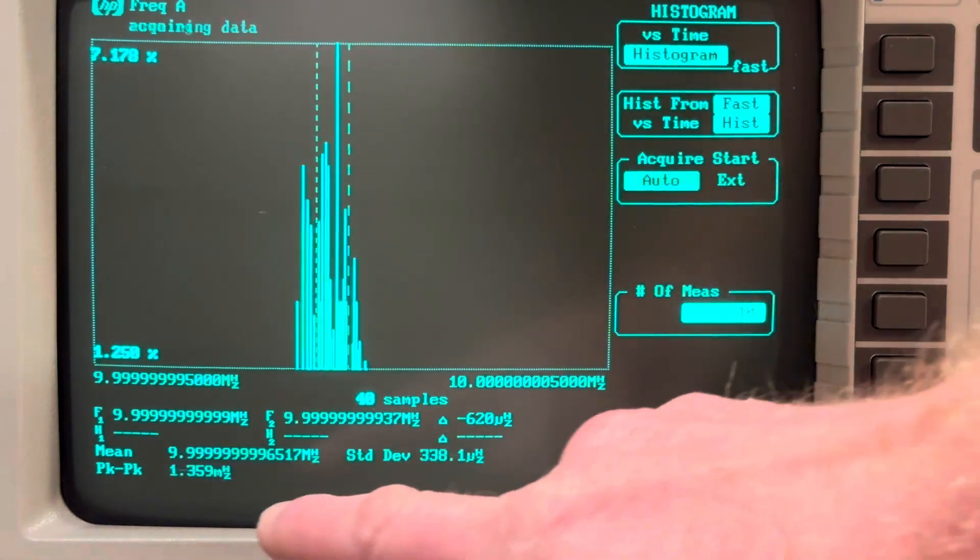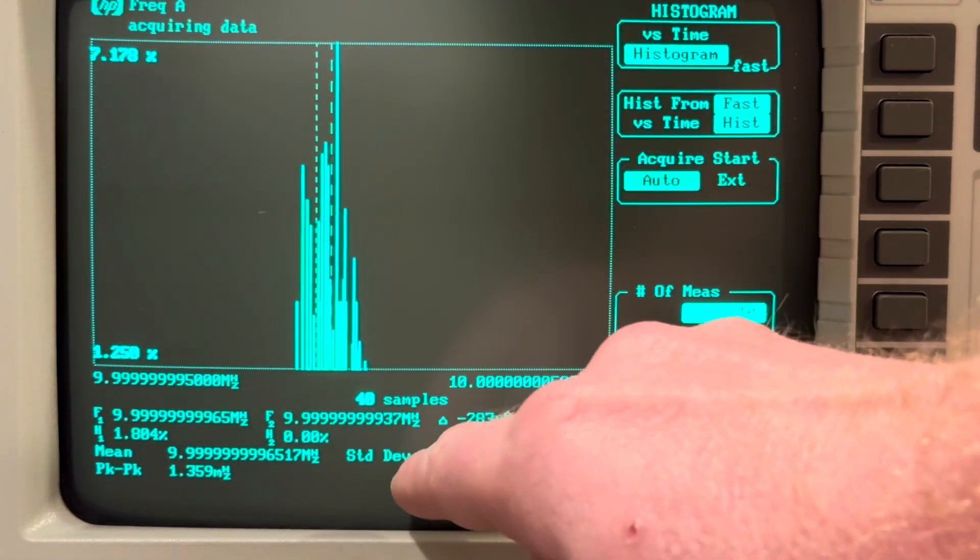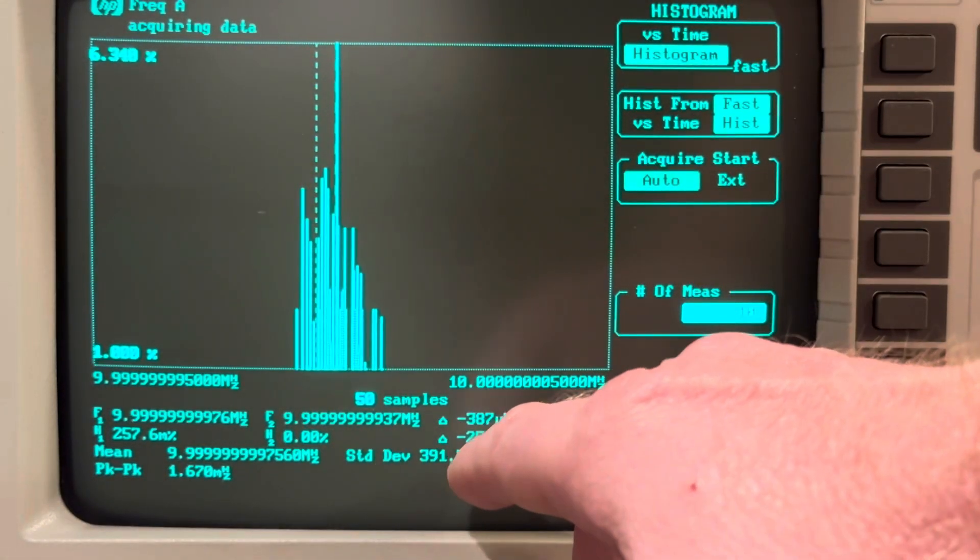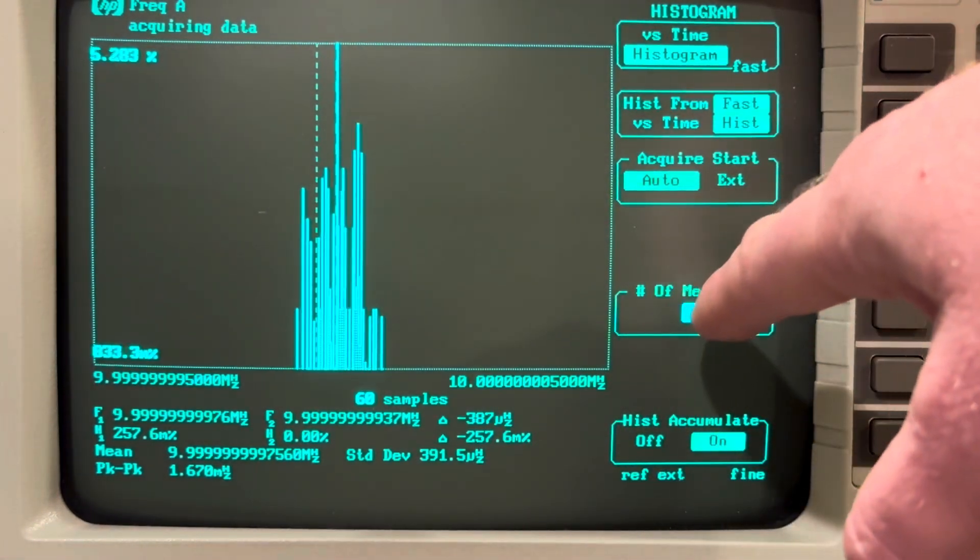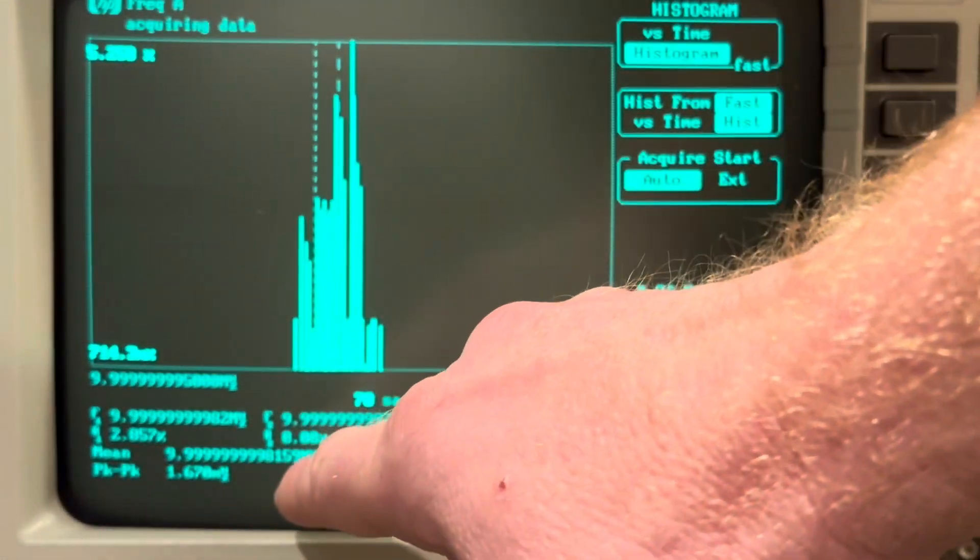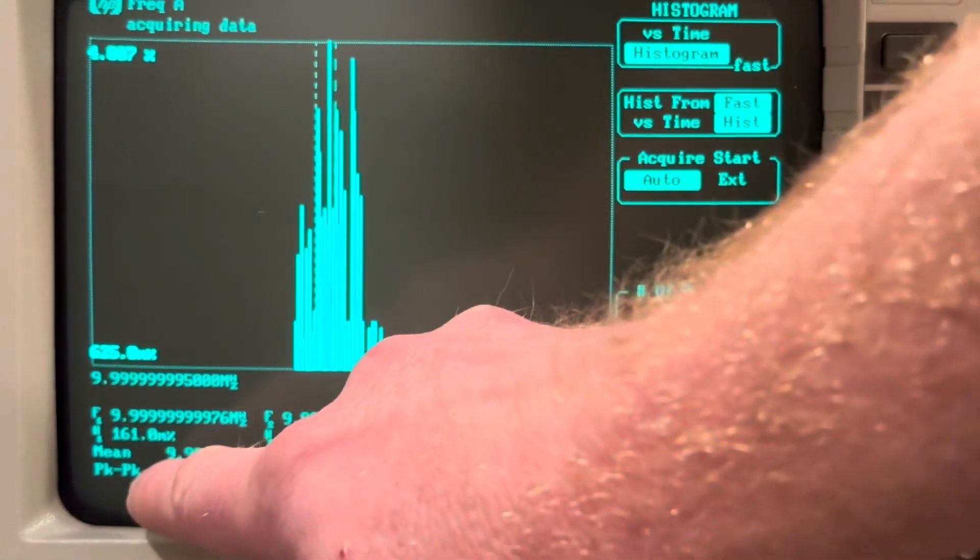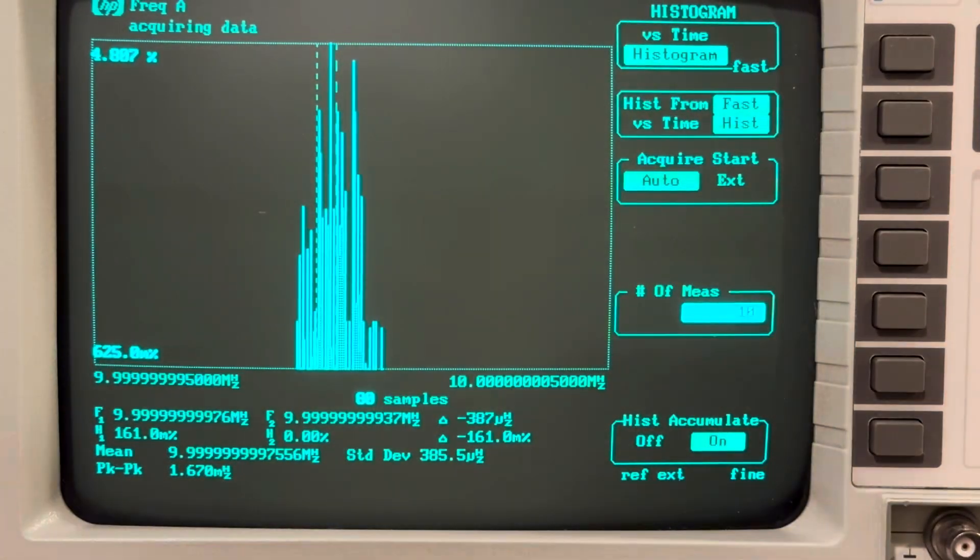So the peak-to-peak and standard deviation, peak-to-peak down here, 1.359 millihertz, and standard deviation, 391.5 microhertz, is of the grouping of the number of samples, number of measurements that it's calculating that from. However, the mean frequency is a continuous update of all accumulated samples. So this frequency here is an average of everything it's sampled.